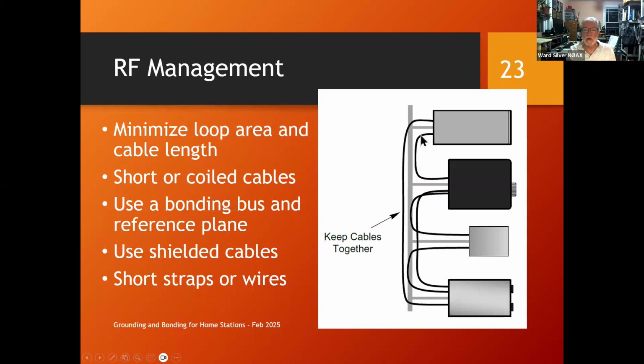Here's your bonding bus or reference plane, whatever you use - a low impedance, electrically short connection. You always want to use shielded cables for audio, control, all that stuff. The only thing that should be unshielded is your power, your 12 volts, and that should be well bypassed at the equipment.